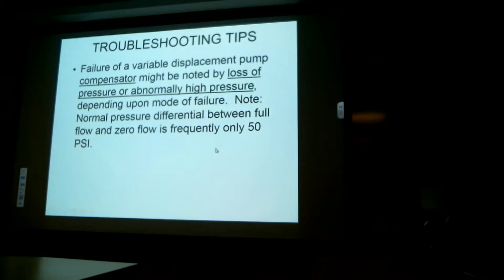It's not like an unloading valve. An unloading valve has got a definite period for kick in and kick out. The pump that has a compensator just delivers enough flow that's sensed by the needs of the system. So it's very difficult to troubleshoot something like that.